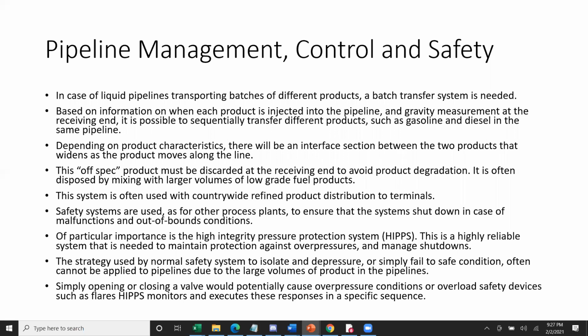A highly reliable system is needed to maintain protection against overpressures and manage shutdowns. The strategy used by normal safety systems, to isolate and depressurize or simply fail-safe to a condition, often cannot be applied to pipelines due to the large volumes of product in the pipelines. Simply opening or closing a valve would potentially cause overpressure conditions and overload safety devices such as flares. HIPPS monitors and executes these responses in a specific sequence.